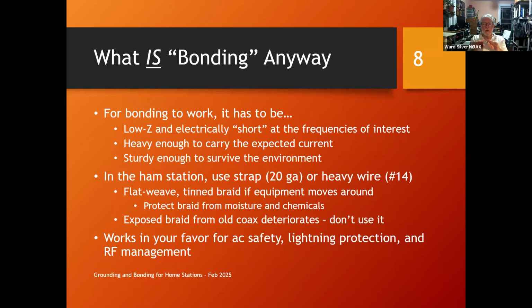Even really wide strap stops being all that effective because the current tends to concentrate at the edges. And so a heavy round wire will work as well as a 1 inch or 1.5 inch strap. You can use that flat weave tinned braid, the silver stuff, if your equipment moves around or you have to continually move the ground connection around.